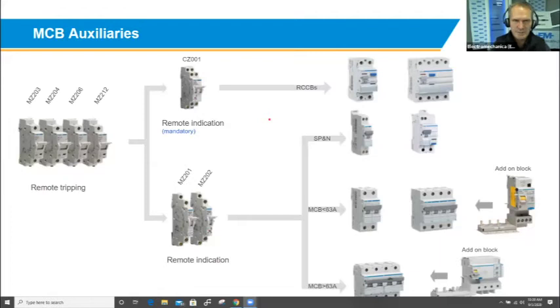You can also add in a, I'm going to share my screen again. You can also add in a UVT, which is an under voltage trip, which is also a good thing to add, because what happens is in the reticulation system that we use in South Africa, especially in the residential area, you've got a 3-phase cable running in front of your house, and it taps off line 1 to house 1, line 2 to house 2, line 3 to house 3, and then line 1 house 4 again, and it goes on like that.